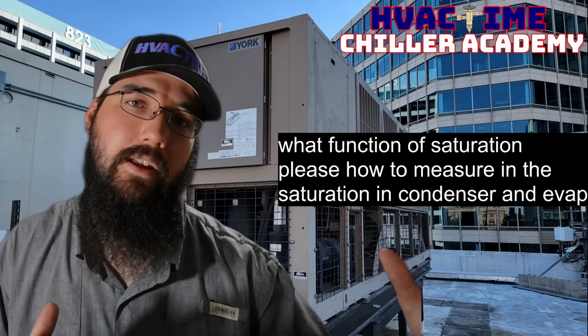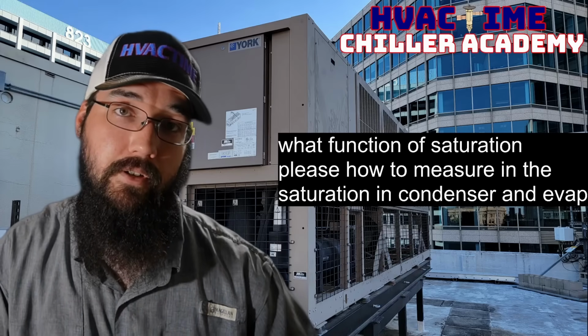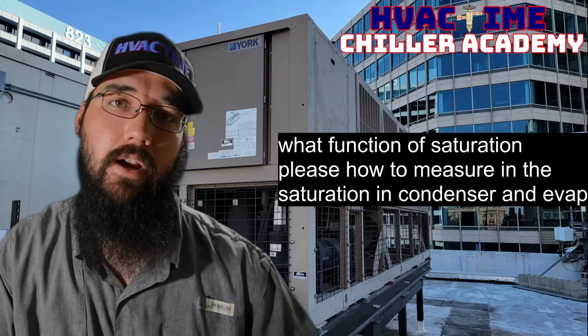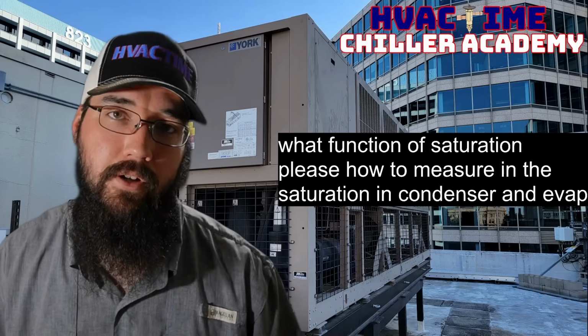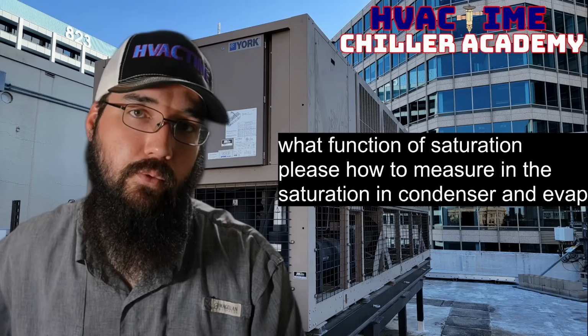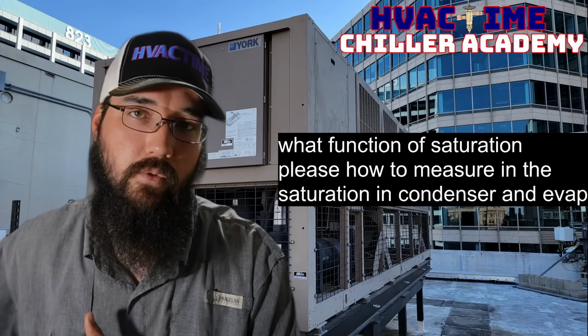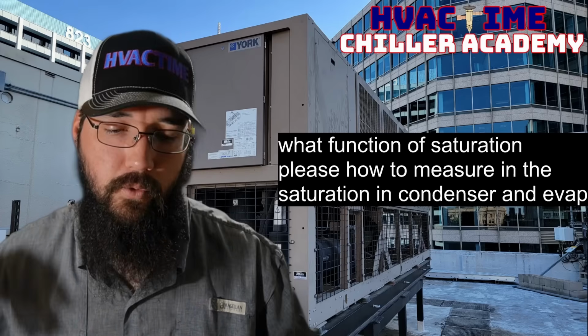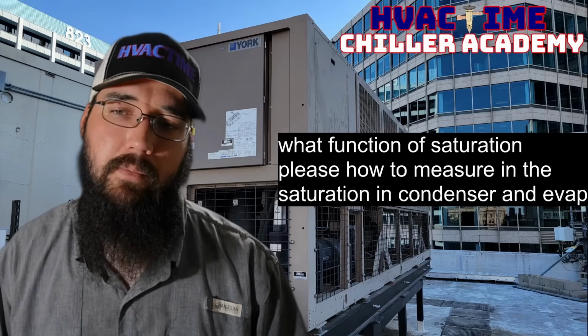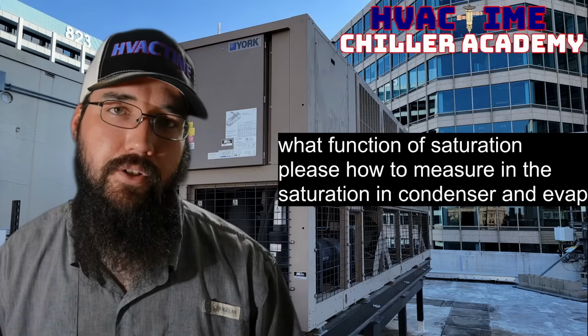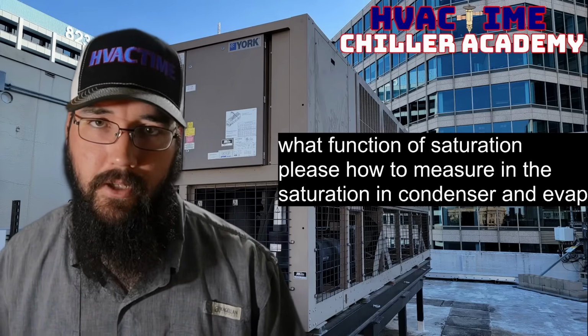And that's how we can take it from, say, the evaporator, which in our case with the chiller is water, right? We can take it from water, put it in refrigerant, and then either move it to somewhere we can put it in air or other water to a cooling tower, whatever the case may be. So every refrigerant has a PT chart, a pressure temperature chart.